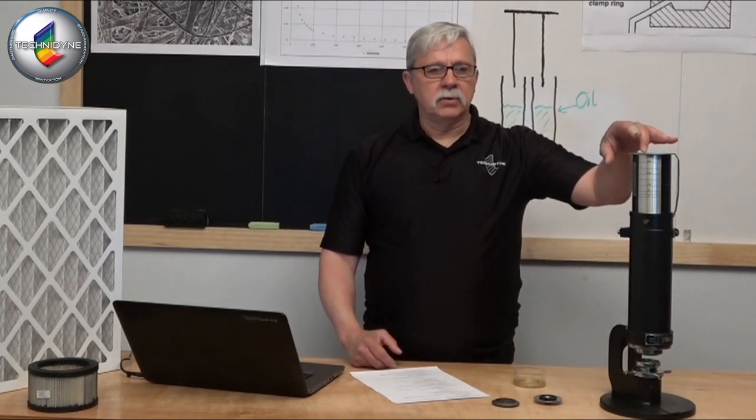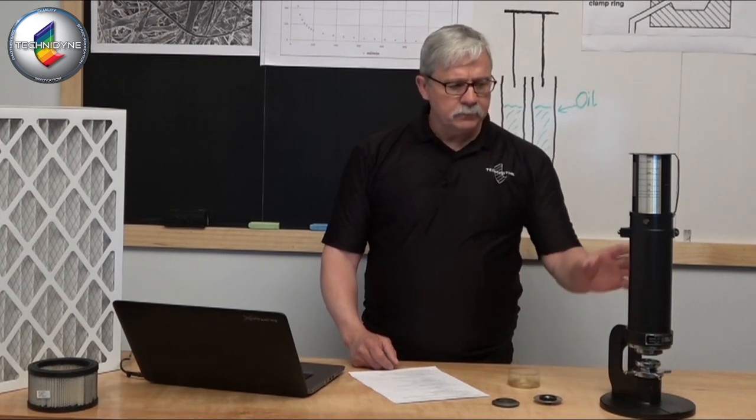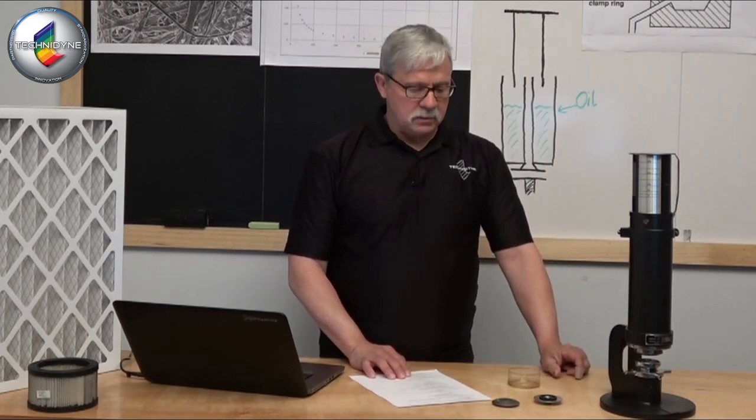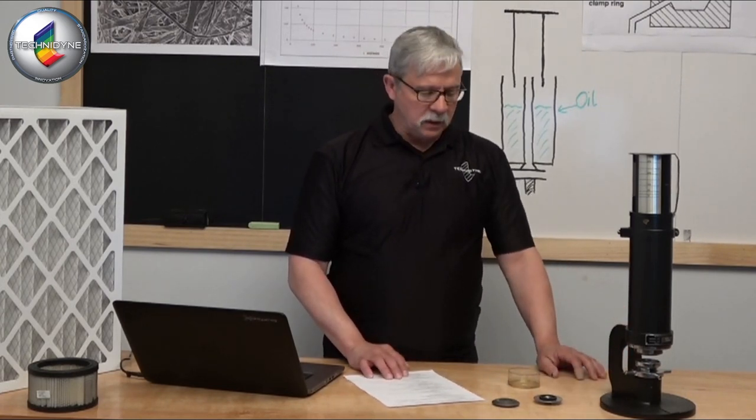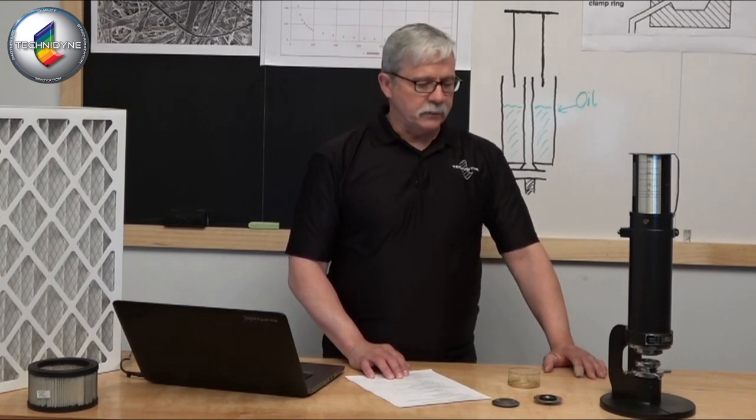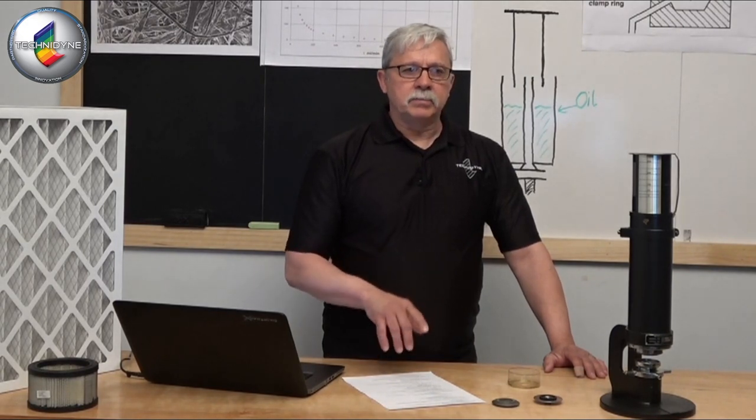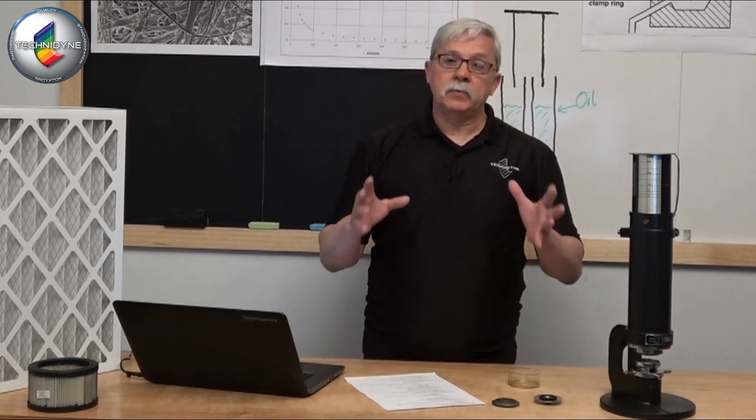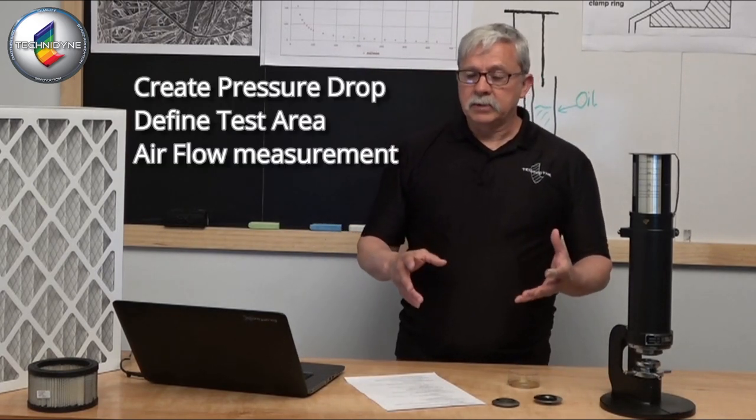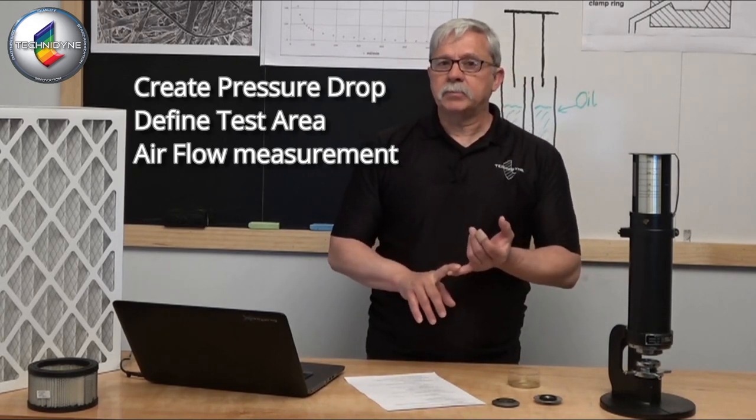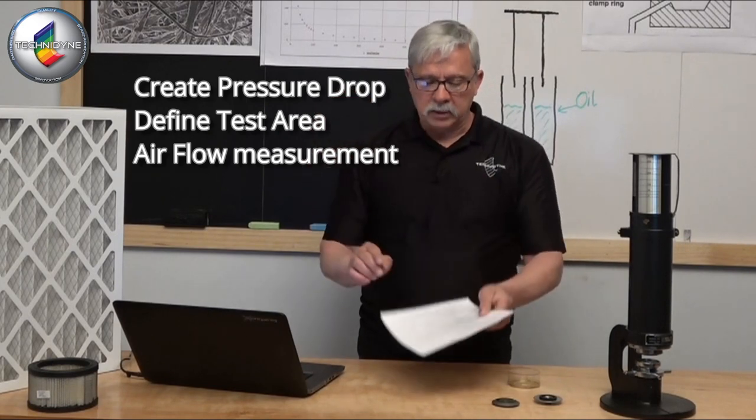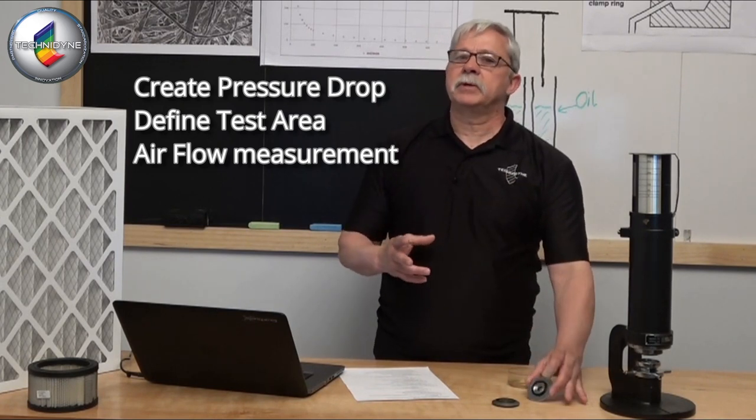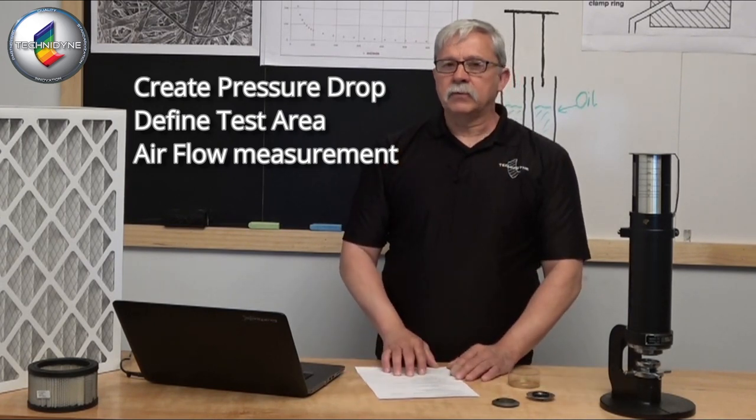So this is the vintage Gurley densometer on display here. This is a fairly old model that we've kept on hand here for some displays and for other reference purposes. In the earlier video I talked to you a little bit about similarities from one method to another. One of those similarities certainly is developing some type of pressure drop across the sample in the z direction. Another similarity is using some type of clamping mechanism so we can define the area that we're going to be forcing that air through.